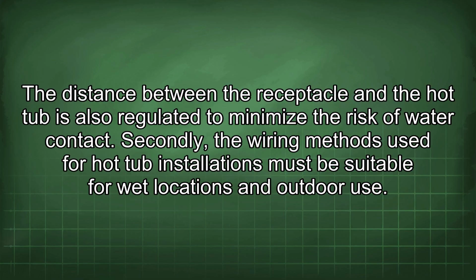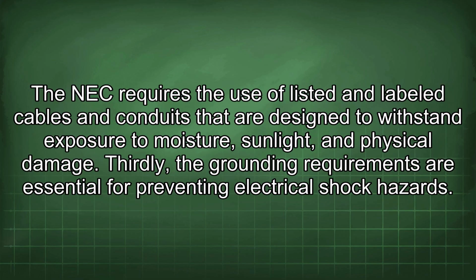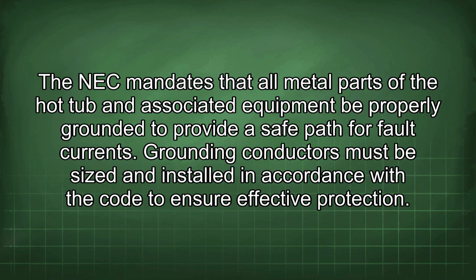Secondly, the wiring methods used for hot tub installations must be suitable for wet locations and outdoor use. The NEC requires the use of listed and labeled cables and conduits that are designed to withstand exposure to moisture, sunlight, and physical damage. Thirdly, the grounding requirements are essential for preventing electrical shock hazards. The NEC mandates that all metal parts of the hot tub and associated equipment be properly grounded to provide a safe path for fault currents.